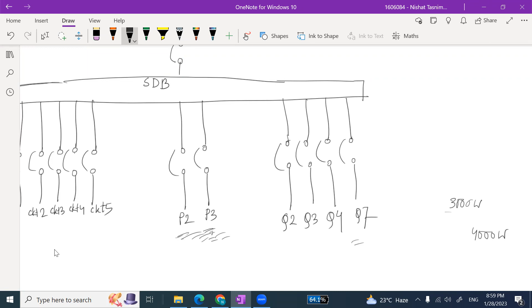Let's say P2 and P3 can support up to 15 ampere. Okay, so we can use a 15 ampere single pole molded circuit breaker. And let's say the Q port supports 20 ampere. So we can use 20 ampere single pole molded circuit breakers.